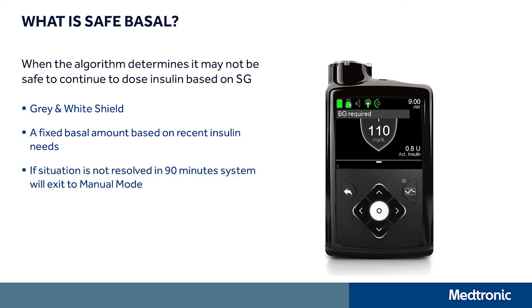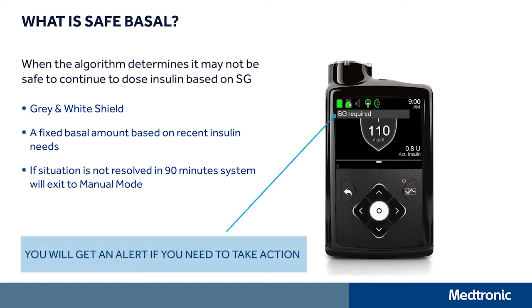Lastly, if the reason why safe basal occurred is not resolved within 90 minutes, the system will exit to manual mode. Rest assured that safe basal may resolve on its own. But if there's something you can do, like enter a BG, your pump will let you know. Simply clear the alert and follow the instructions on the screen.